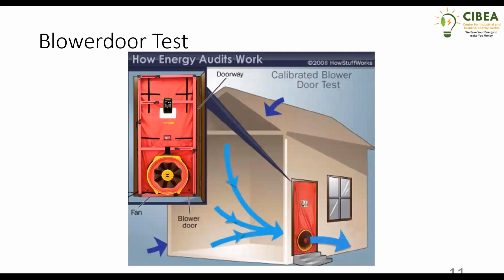So once we are clear about how energy saving and energy wastage control are different, let me introduce you to a blower door device which can be used to measure the energy wastage. We have a calibrated whole kit of blower door system, which we have used on single story residential and commercial buildings, but it can be used for multi-story buildings if there are split air conditioners in the rooms. So we can do testing with this one kit, but for bigger buildings with HVAC systems, we need bigger blower door systems to measure energy wastage by leakage.